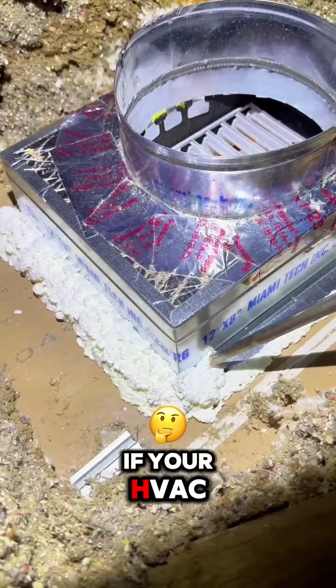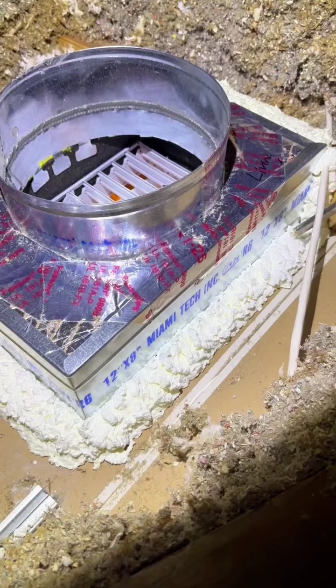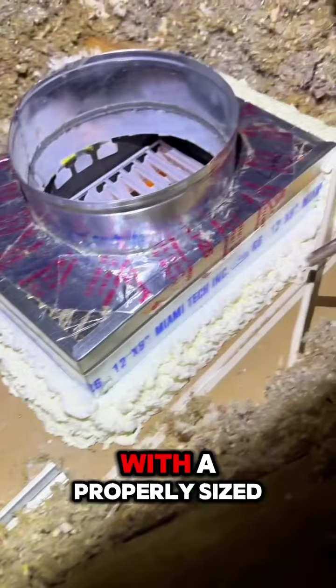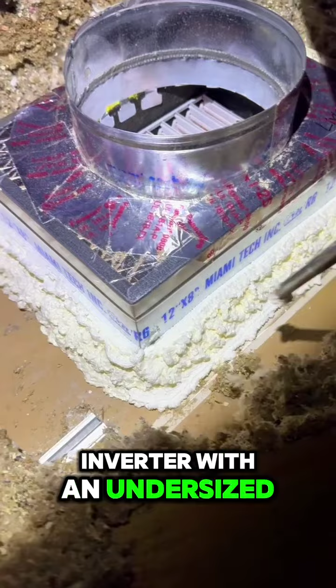As far as HVAC goes, here's the thing: your system isn't going to work right if your ductwork isn't right. It doesn't matter if you have the cleanest install in the world with an inverter 20 SEER system—if your duct system is undersized, it's not going to work right. I think we over-focus on the equipment. I'd rather have a single-stage, 14 SEER, even straight-cool system with a properly sized and properly installed duct system than a 20 SEER inverter with an undersized or poorly designed duct system.